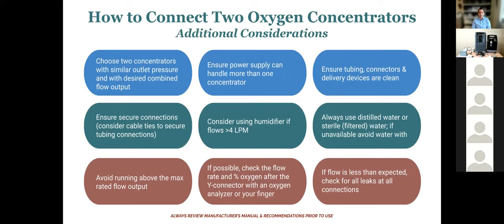When you're doing this, trying to choose two concentrators with similar outlet pressures and with the desired combined flow output is important. You're going to have two devices potentially plugged into the same power supply. So make sure that it's not going to be too much to blow a fuse. And if you can have them on different outlets, even better. Make sure that the tubing and the connectors you're using are clean and are large enough that they're not going to impose unnecessary or problematic resistance.